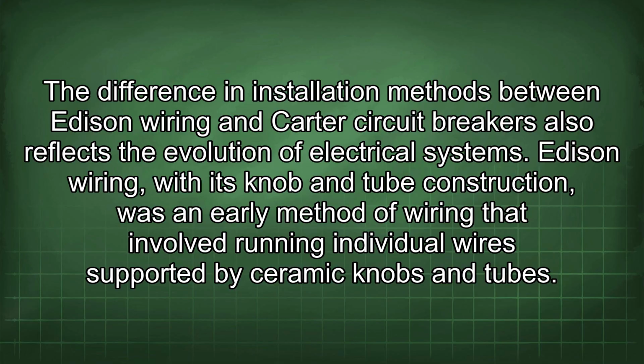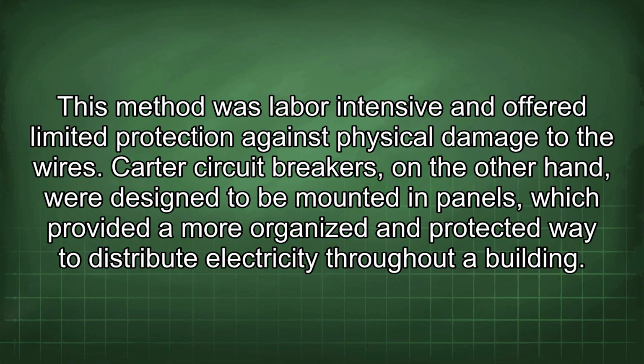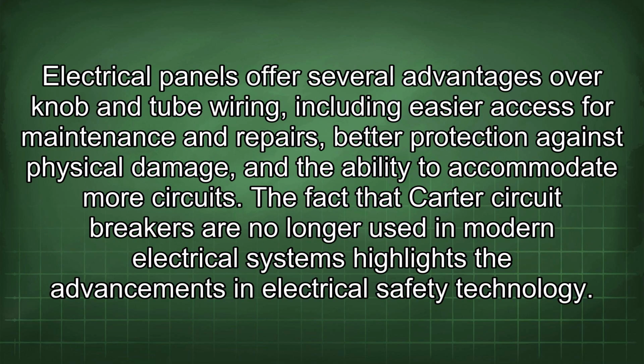Edison wiring, with its knob and tube construction, was an early method of wiring that involved running individual wires supported by ceramic knobs and tubes. This method was labor-intensive and offered limited protection against physical damage to the wires. Carter circuit breakers, on the other hand, were designed to be mounted in panels, which provided a more organized and protected way to distribute electricity throughout a building. Electrical panels offer several advantages over knob and tube wiring, including easier access for maintenance and repairs, better protection against physical damage, and the ability to accommodate more circuits.